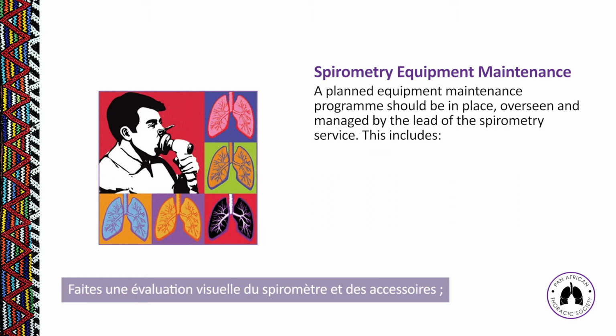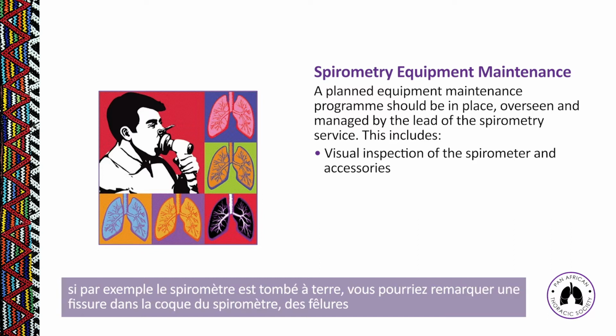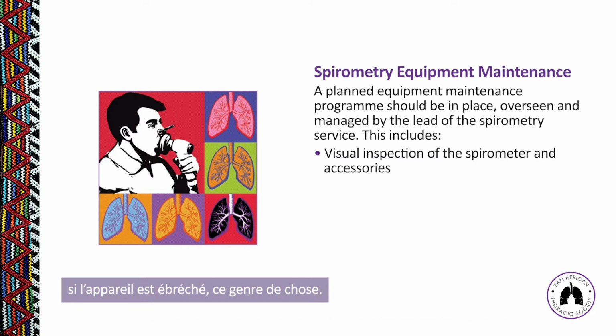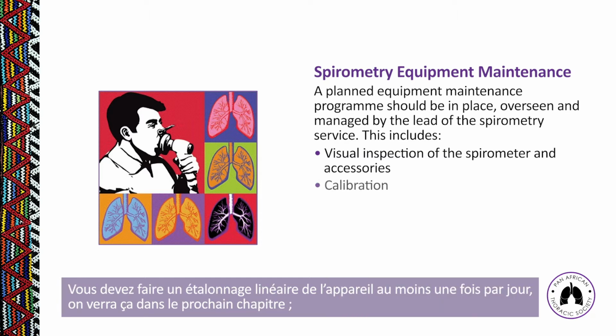You would do a visual inspection of the spirometer and accessories. So if the spirometer, for example, has been dropped, you may see a crack in the housing. You'll be able to see if there's any damage, any cracks, any chips out of the spirometer, things like that. You need to conduct at least a daily linearity calibration check, which you'll learn about in the next chapter.